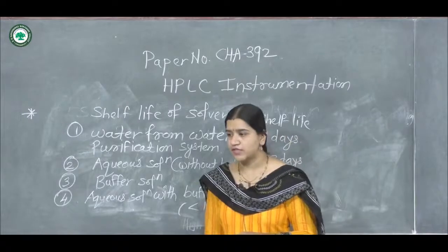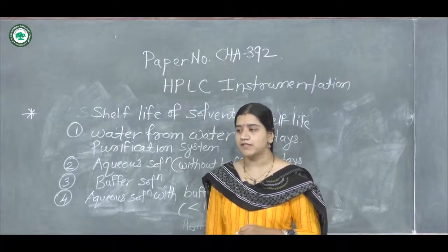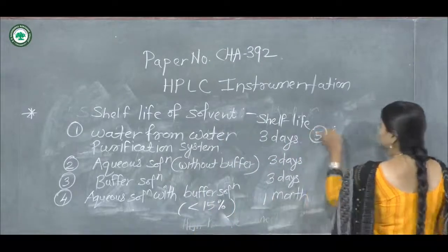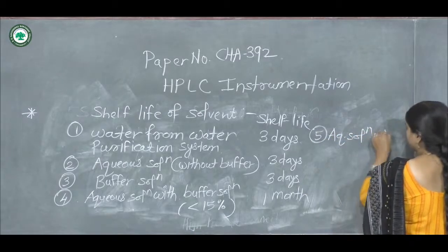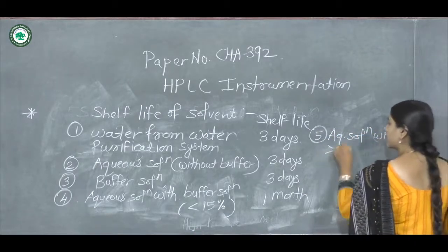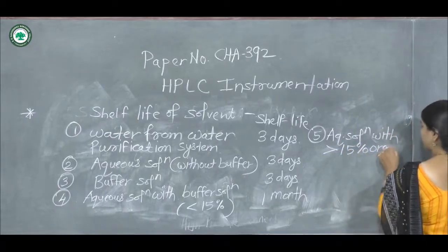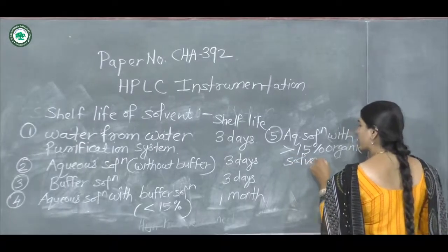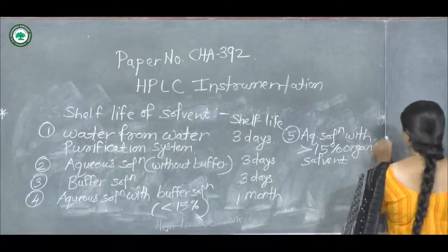Whenever you are using the aqueous solution with greater than 15% of the organic solvent, then it has a shelf life of 3 months.